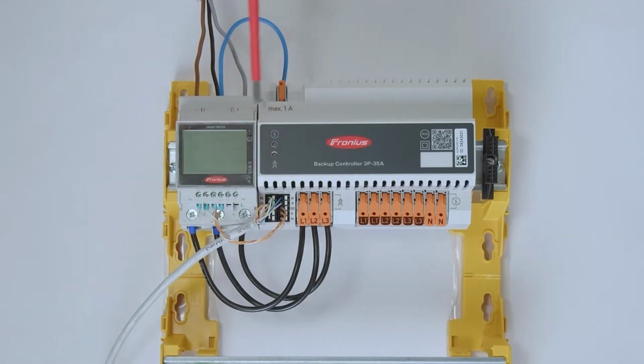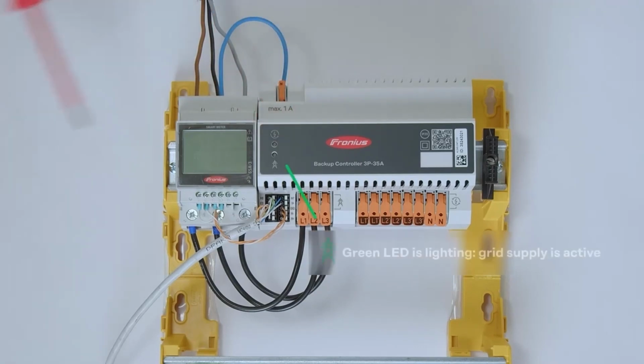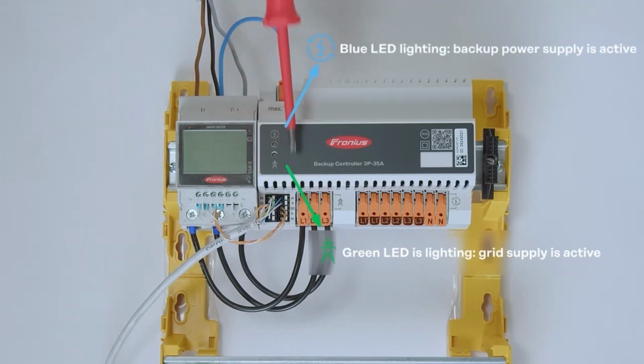Furthermore, we have a little interface on the backup controller, and this will tell you from the front side in which mode the backup controller currently is. So we have one LED for the grid parallel mode and one LED for the backup power mode. So that means that even the end customer can directly see from the front side of the device in which mode the backup controller actually is. And depending on the current situation, the backup controller will now switch automatically between backup and grid parallel mode.